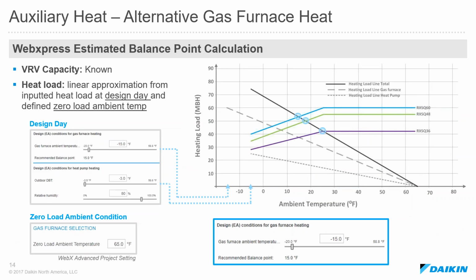So we've introduced this concept of balance point. How do we determine what that balance point is? Fortunately, we have Webxpress, the selection software that's going to do it for us with some information that we provide to it. So obviously it's going to know what the capacity of the VRV systems are. That's already built into the selection tool. And once we enter in what the design day temperature is and what that heating load is, it's going to determine a heating load curve. So it assumes by default at 65 degrees outside that there's no heating load. That's a pretty standard ASHRAE condition, 65 degrees, no heating load. And then you're assigning that heating load as well as when that heating load is occurring outside. And it's just going to draw a linear line between those two points and tell you where they intersect.